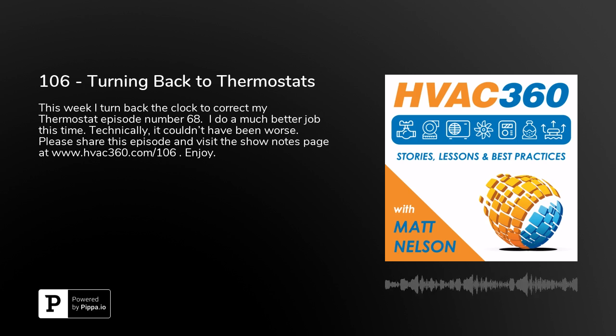And again, that is the range that you would expect to find in these thermostats. A lot of times it's a little confusing, because you set the set point, that 70 degrees, but it offsets 2 degrees automatically. As a user, you don't know what the 68 and 72 are. You just set the 70, and you're like, why is it bouncing between 68 and 70? I wanted 70. So they start cranking it up, and it's hard to understand sometimes.